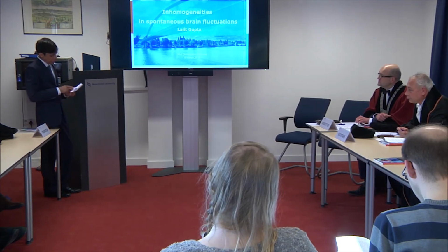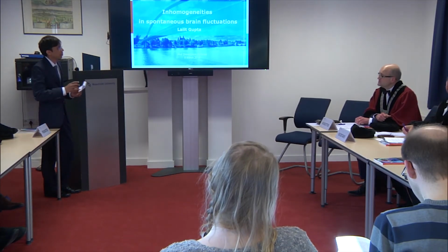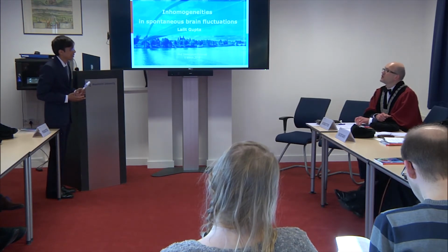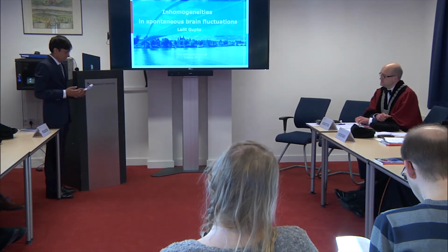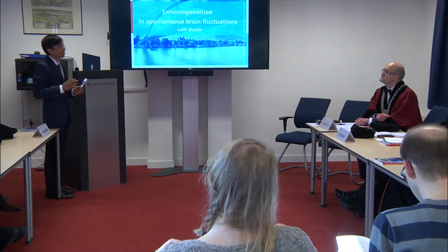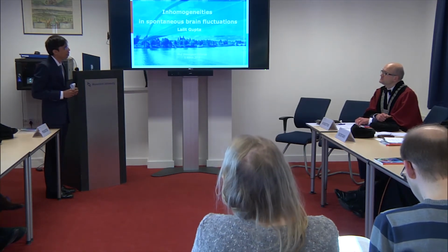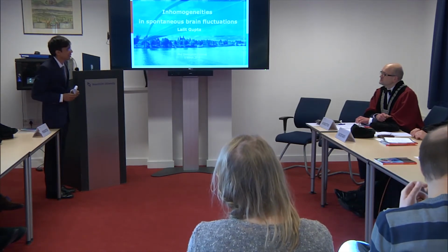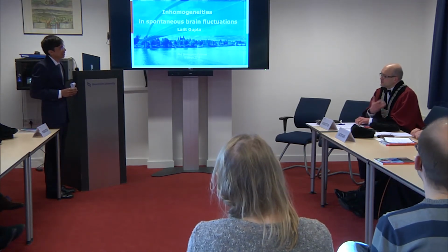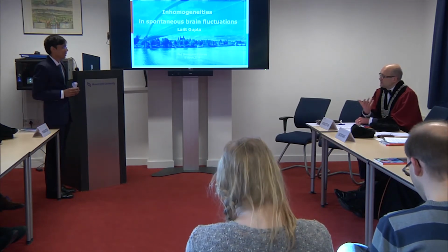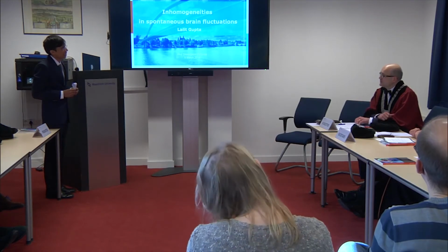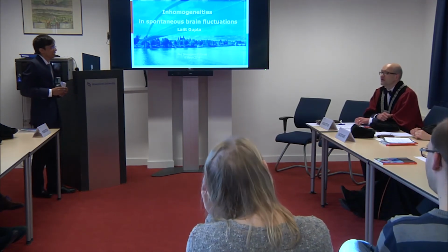When I say health wearables here, I would say they are medical devices, not lifestyle devices. The wearables currently thought of in the market are more lifestyle devices, and they should not be used as medical devices. So you're saying it's about clinically valid wearables for some areas? Yes. But then they would be classified as medical devices. As medical devices. Yes.